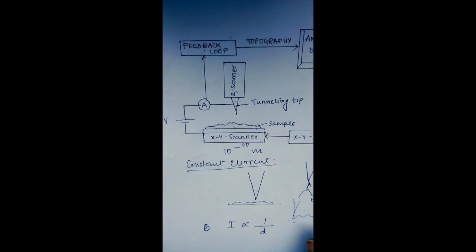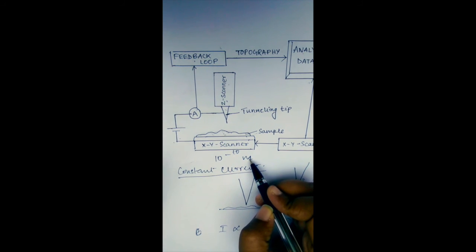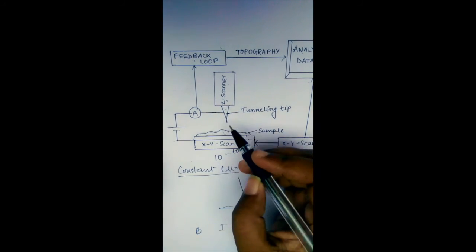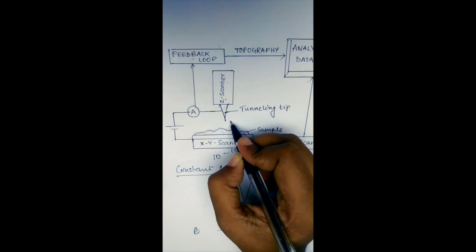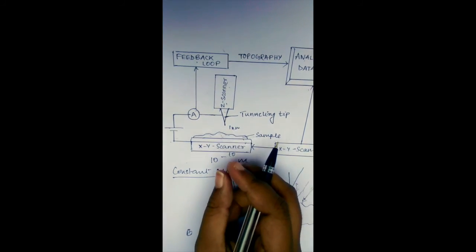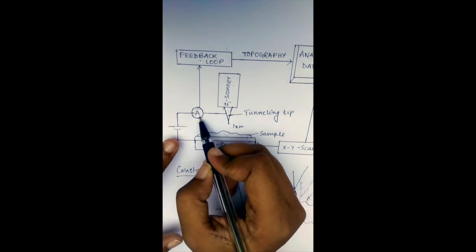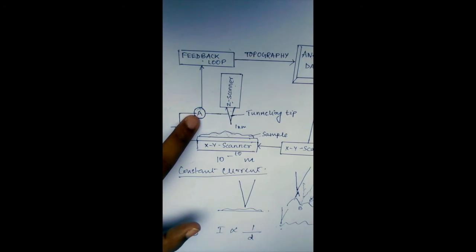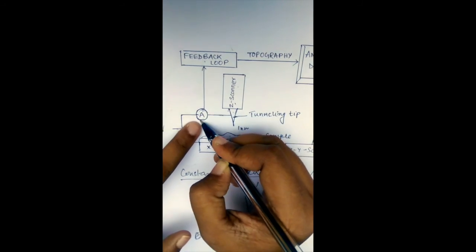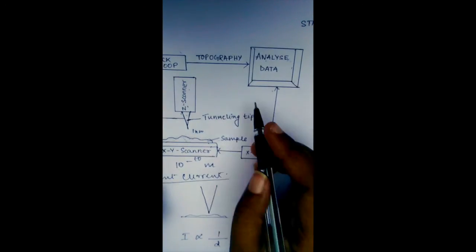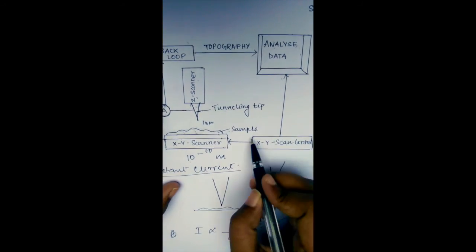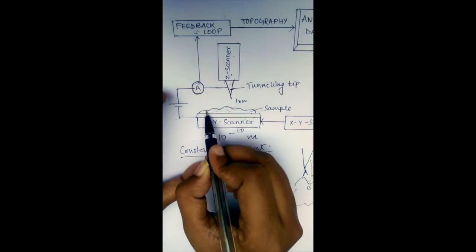The phenomenon of quantum tunneling is used here, and the sample must have a conducting surface. The tunneling tip is also very thin, on the order of 1 nanometer, so that the tunneling effect can take place. An amplifier is included because the current detected is usually very weak. The amplifier boosts the current and sends it to the feedback loop, and from there a computing device processes the data. This is the scanner on which the sample is scanned.